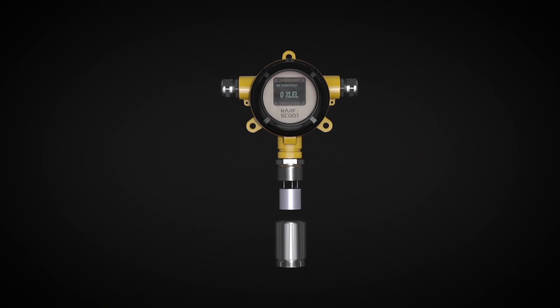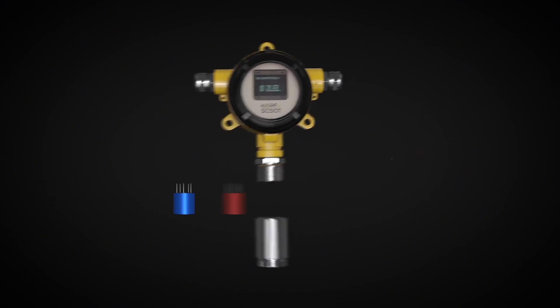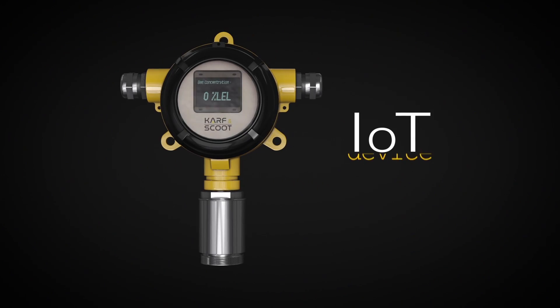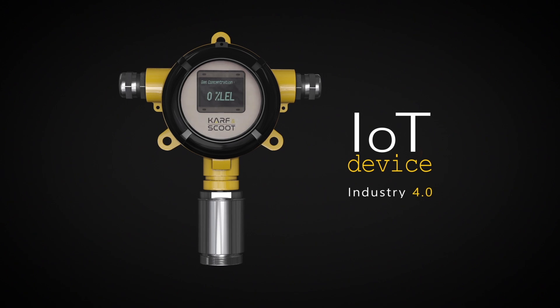Catalytic, infrared, and electrochemical sensor heads are available depending on customer needs. These sensor heads can be easily calibrated and are replaceable. With its expand bus structure, Karf Scoot is a modular product that's able to communicate with all systems that use RS-232, RS-485, and Ethernet communication protocols. You can transform your gas detector into an IoT device and upgrade your safety to Industry 4.0 level, thanks to this expand bus structure.